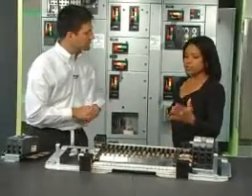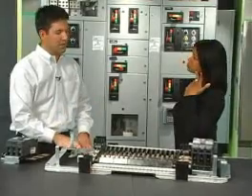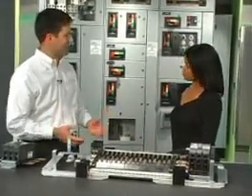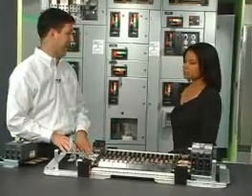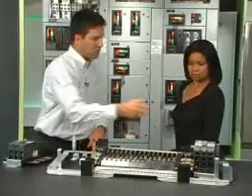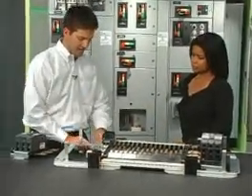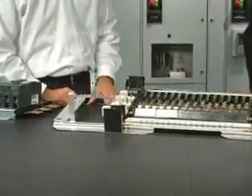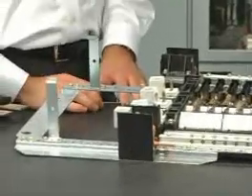Now, when would you actually add features? Sure. Well, that's one of the beauties of the Pro-Stock panel board. Unlike factory assembled panel boards that come out of the factory as is, and it's really difficult to add to it, the Pro-Stock gives you some flexibility where you can add into the future. And that's just as easy as it was to add the main breaker. All you do is on these studs down here, you can add lugs. So again, bolt them down, away you go. You can wire to another panel, wire to an application, or whatever it is you may need.